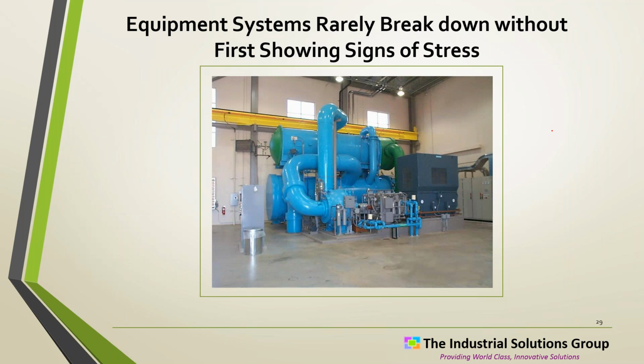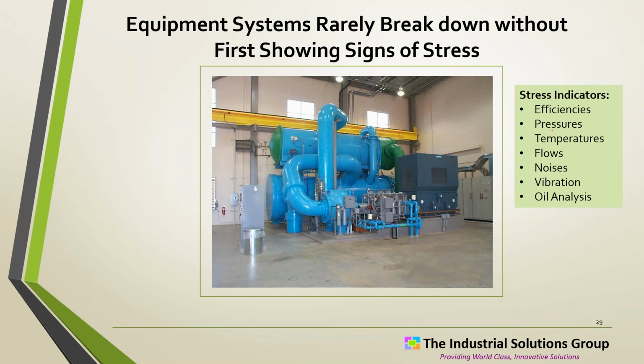Great looking chiller here. It's a large chiller and great looking, but how do we know that it's not showing some signs of stress? Can't tell by looking at it, because obviously they're paying a lot of attention here to housekeeping, but that doesn't tell you how these pumps are working on the compressors and whether those heat exchange surfaces are clean. And there are a lot of stress indicators that a good control system can pull out for you. It can look at efficiencies. What's a kilowatts per ton? What's a kilowatts per kilowatt of refrigeration? Are you at design? Are you not at design? What kind of pressures are you dealing with?